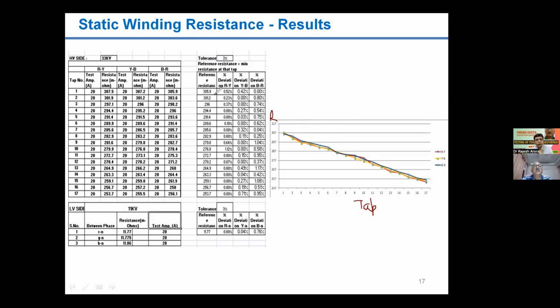If you see the table, different testing kits have different types of variations. Some may take variations from the minimum value of the resistance, meaning the phase having the least value of resistance, and some may calculate variations on the basis of the mean or average value of the resistance arrived for all the three windings. That way the deviations or variations are recorded, and accordingly the curves are plotted. So this is a very important tool to know the health of the OLTC of the transformer.